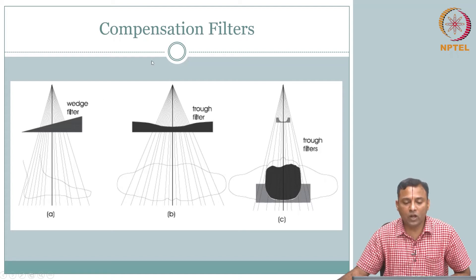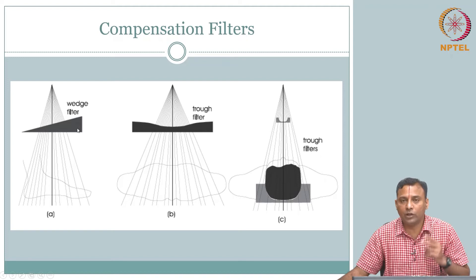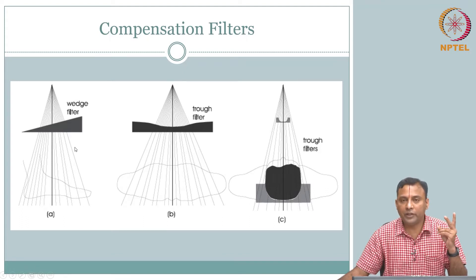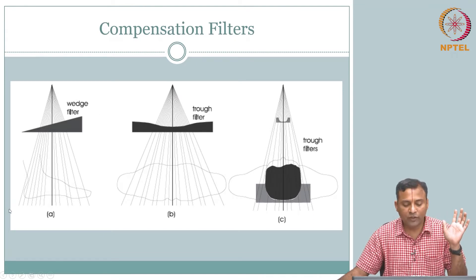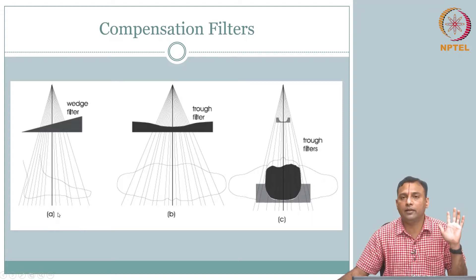So in this case, we know a priori that there is a path length difference because of the shape of the object. Therefore you could come up with a compensation filter where you essentially equalize the combined path length — the tissue path plus the filter path together — so that more or less the total path length is the same. Therefore, whatever loss you get is proportional only to your differential material property. This is why it is called a compensation filter: you are compensating for the change in path length through the medium.